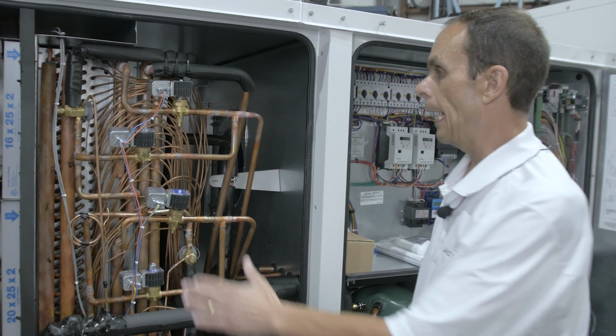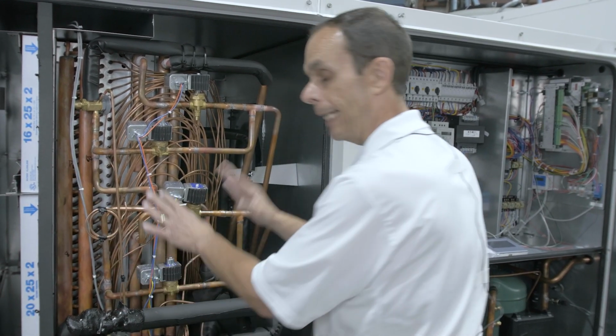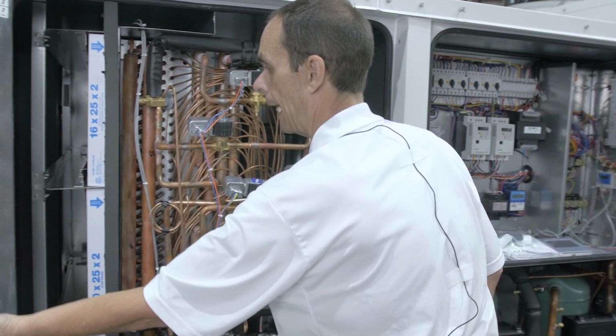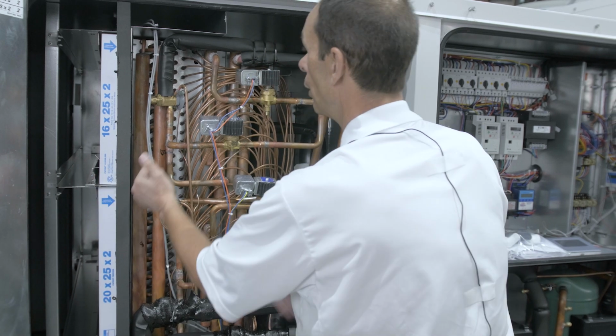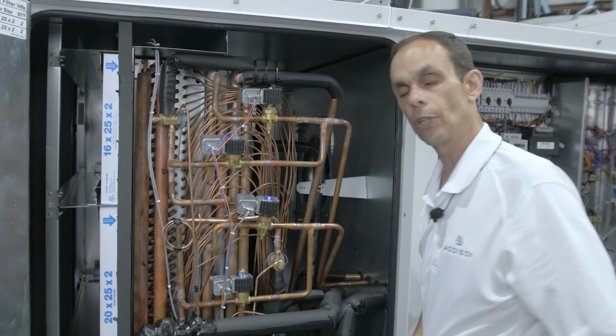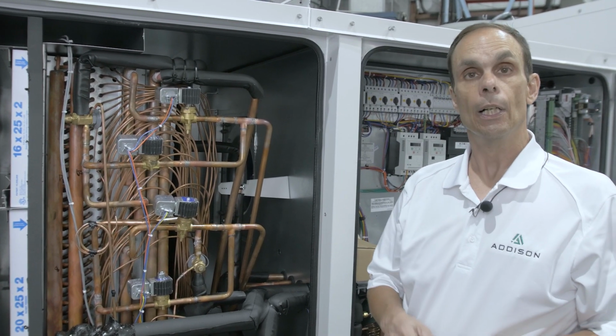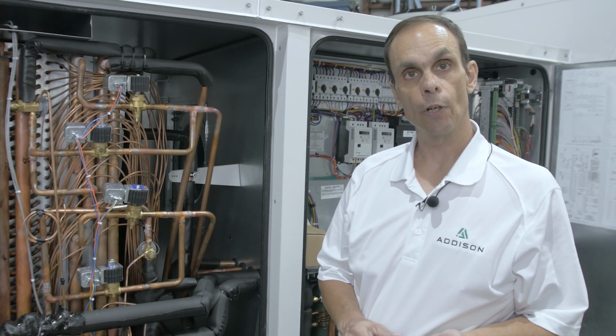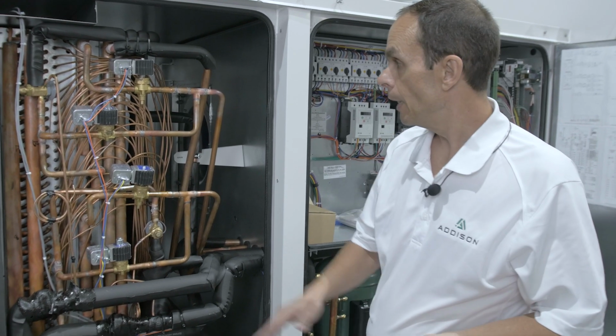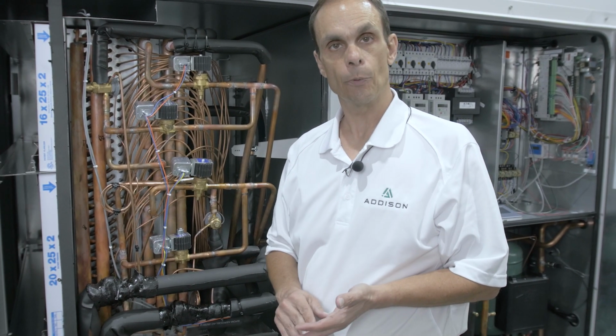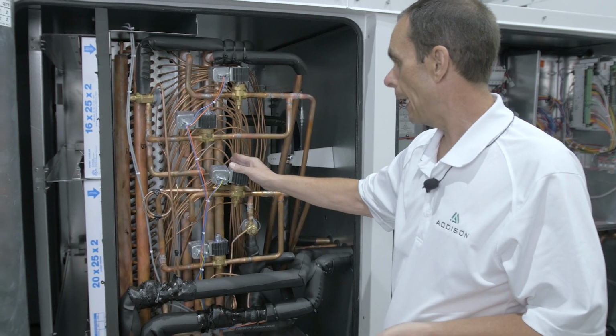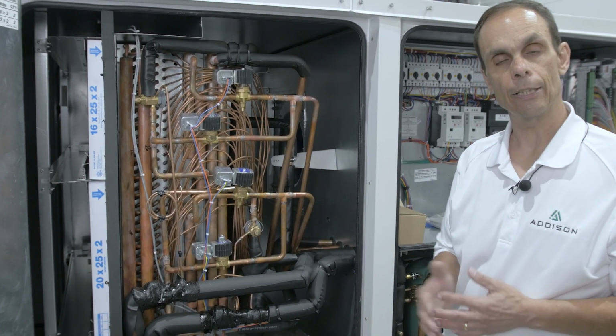So basically, as your coils are laid in here, to identify your coils, as the outside air comes in through the filters, your first set of coil that it's going to hit is your DX coil. That could either be a 4-row coil or a 6-row coil. The coil in the center will be a subcooling coil, and the last coil before it hits the supply fan is going to be your reheat coil.